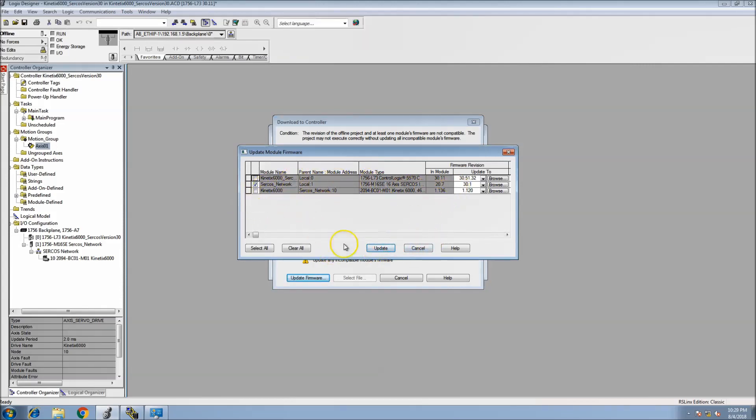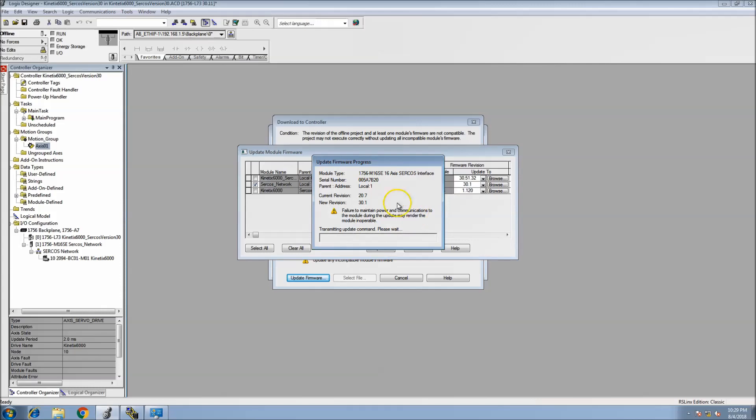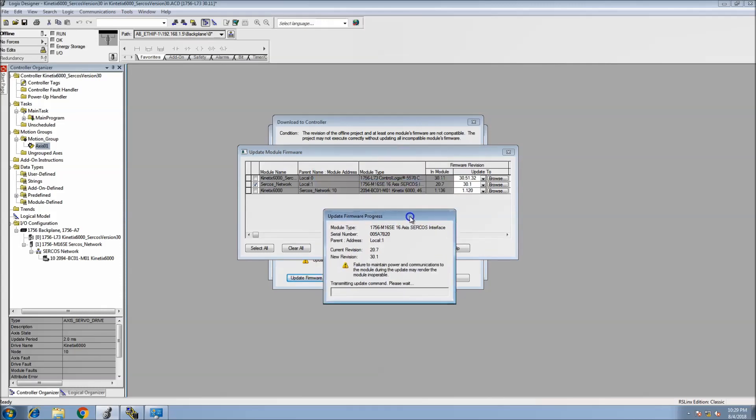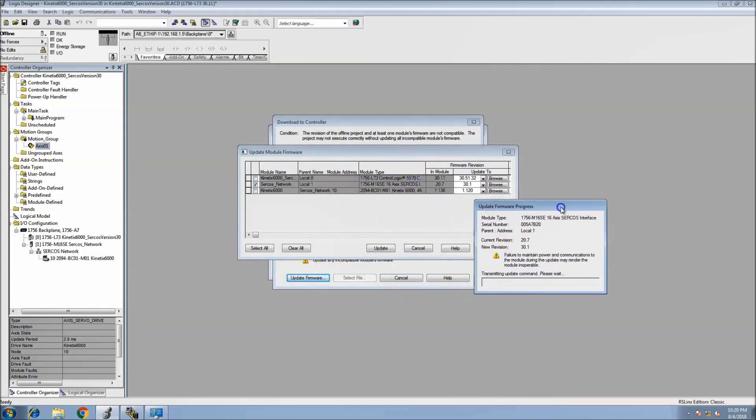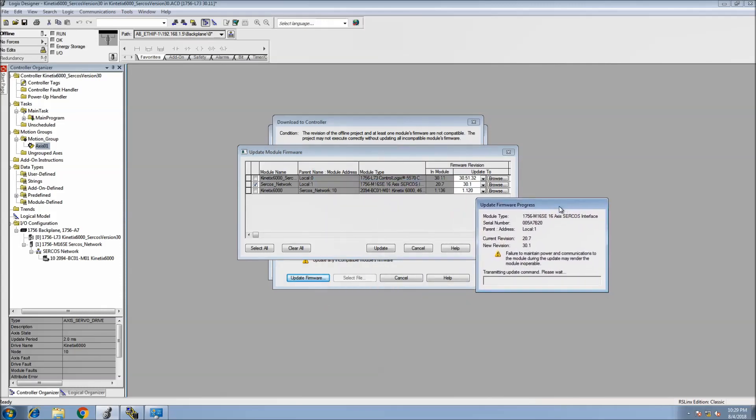Not sure why it would ask that because it is in the correct firmware. That's because my SERCOS card is not at that firmware, which makes perfect sense. At that point you can just update your SERCOS card.